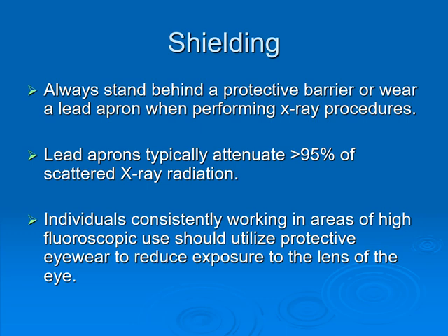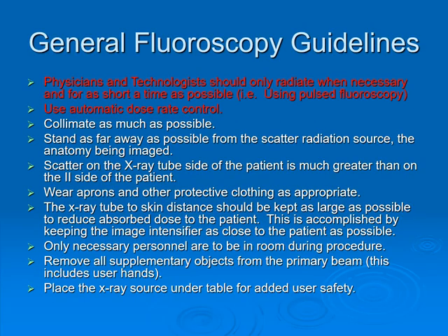Individuals consistently working in areas of high fluoroscopic use should utilize protective eyewear to reduce exposure to the lens of the eye. General fluoroscopy guidelines. Physicians and technologists should only radiate when necessary and for as short a time as possible. For example, utilize pulse fluoroscopy. In addition, automatic dose rate control should be used.